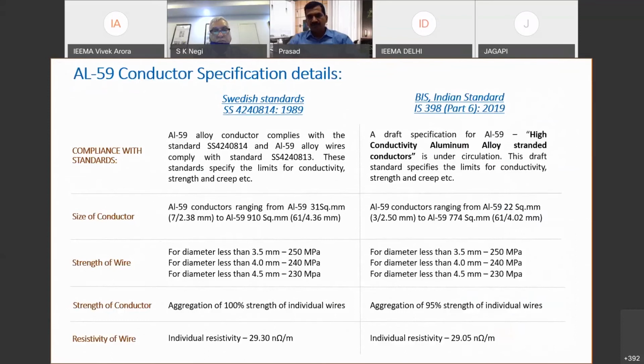Now we would like to focus on a summary of both the specifications, the Swedish standard 1989, the latest version, and the IS standard, for which we will have the official published copy in a very short time. As far as sizes are concerned, the Swedish standard offers right from 7/2.38 mm, like 31 square mm, for distribution conductor size, to 910 square mm, the highest size in transmission conductor. Whereas in the BIS standard, we have 22 square mm, a very low size, 3/2.5 mm, and 774 square mm, 61/4.02 mm size. As far as strength of the wires is concerned, both the standards have parity.